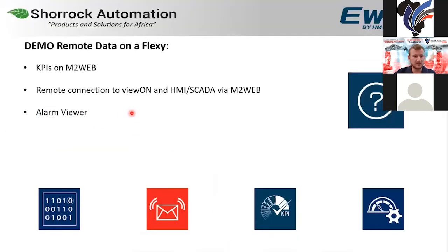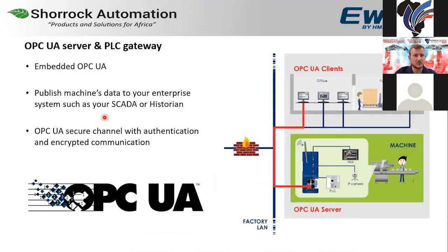And moving back into the presentation. Okay, so I've already showed all of that. So the Ewon then also comes with the OPC UA server as well as the client service. In this instance, we could connect over the native IIoT drivers to PLCs and HMIs that, for instance, don't support OPC UA, and then share this data as an OPC UA server to a Wonderware or a Movicon SCADA system, for instance, which would act as a client.